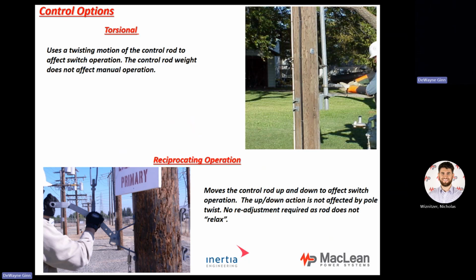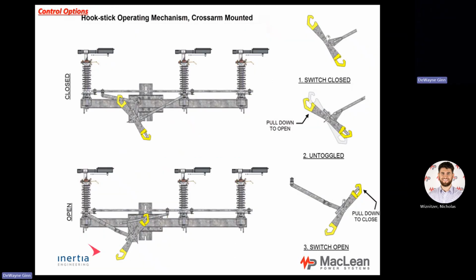We recommend, though, the reciprocating, which is called a pump handle, which is an up and down motion. The up and down motion allows the switch to open and close very, very well. Also, as I talked about, as the wood starts curing and twisting, that twisting motion doesn't affect my operation of that switch. I can still operate it without any problems. So there's no adjustment required at that point. Again, here's another control mechanism, the hook stick. Basically all I do is take a hook stick in the air, operate the switch, and it's open and closed. Again, it's very much a plug and play situation where I just put the switch on the pole. I don't put a down rod in anymore for the control handle, and I'm done.